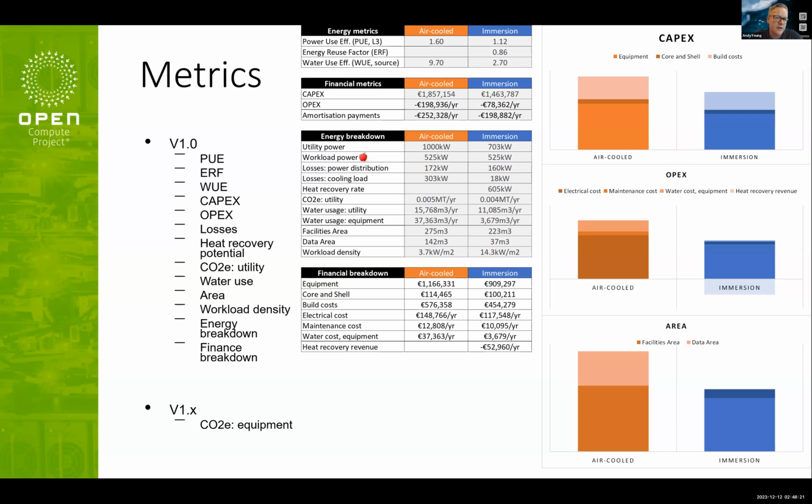So we compare the high-level metrics for energy efficiency, energy recovery potential, and water usage. Those are the top three. I think these are the same three that have been preferenced and now mandated by the German government for new data centers going forwards above a certain scale. And of course, for the business case, we also have information here for the CapEx impact and the OpEx impact of the facilities based on these two alternate technologies. In this case, it's a greenfield site that we're assessing.